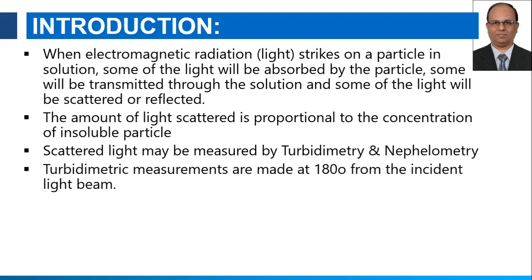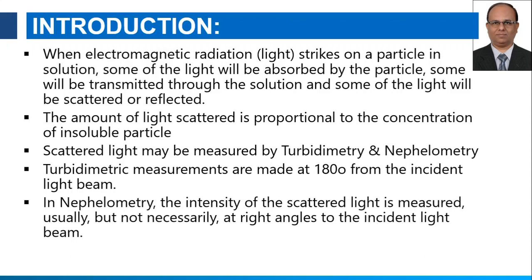Turbidometric measurements are made at 180 degrees from the incident beam of radiation, that is the source. While in Nephelometry, the intensity of the scattered light is measured usually — but not necessarily — at a right angle to the incident light beam.